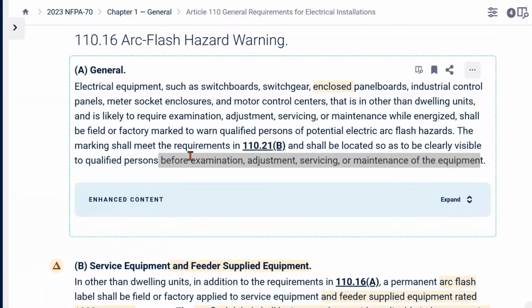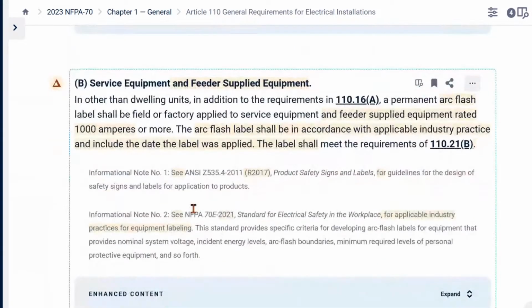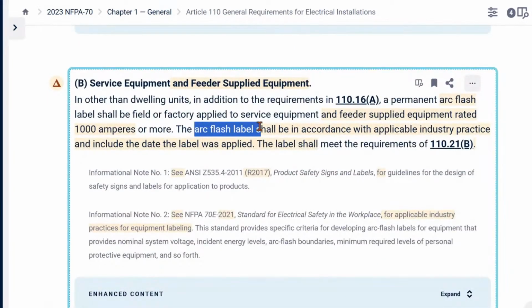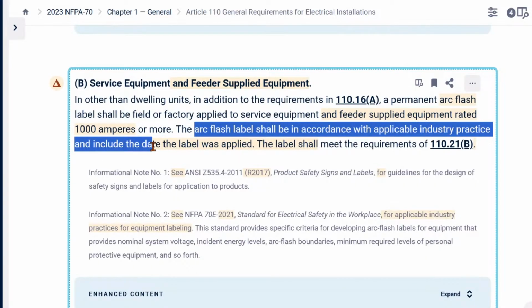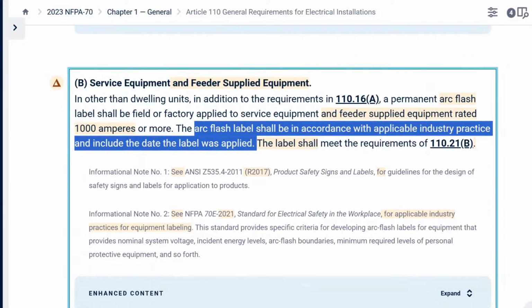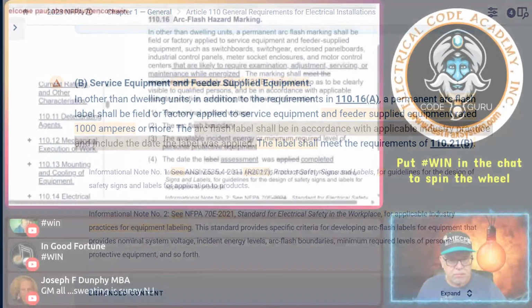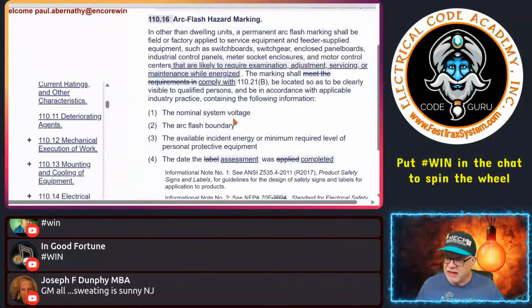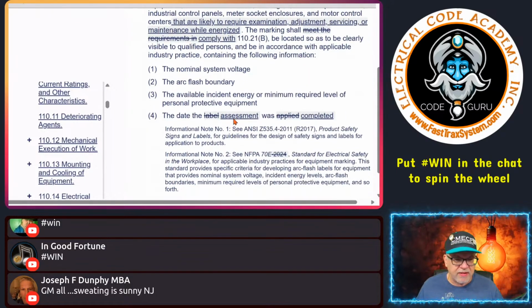You'll notice down here, in the 2023 version on screen, it says the arc flash label shall be in accordance with applicable industry practices and include the date the label was applied. The reason it changes is, here it now says the date the label assessment was completed.